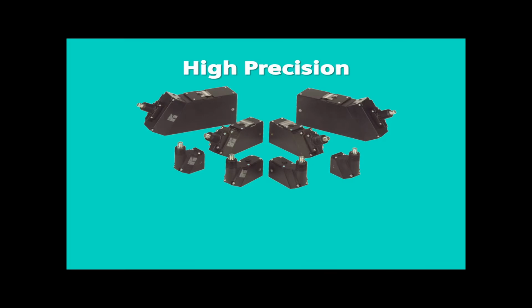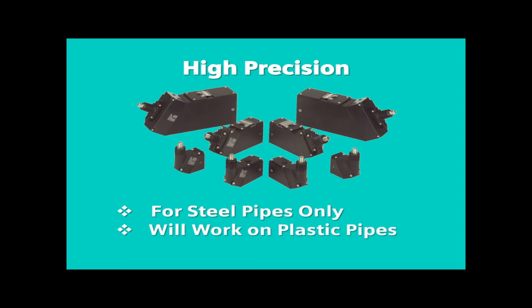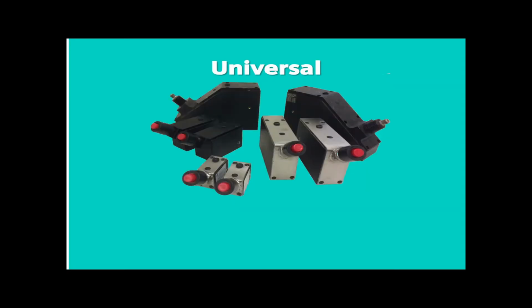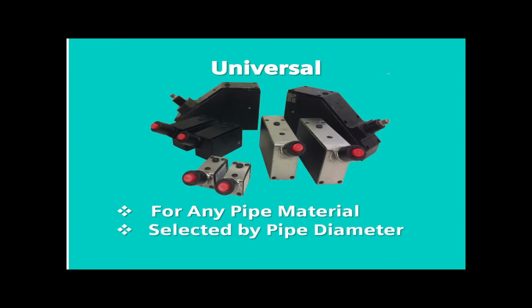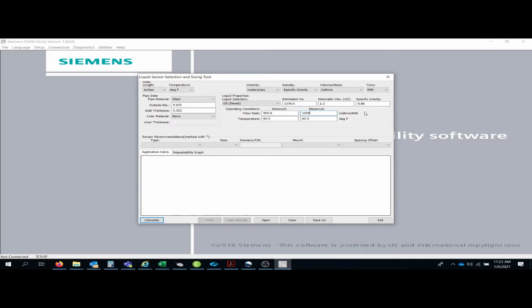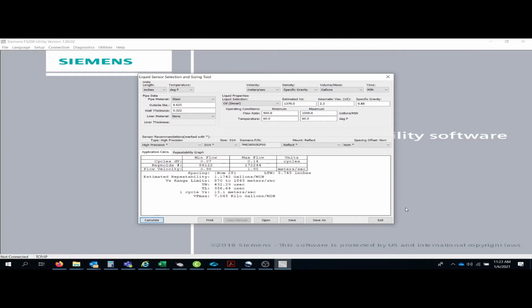High precision sensors are designed for use on steel pipes, though they can also be used on plastic pipe. They are selected based on the pipe's wall thickness. Universal sensors are designed to be used on any pipe material. They're selected based on the pipe's diameter. The FS200 utility program can be used to determine the best type and size sensor for your specific pipe.